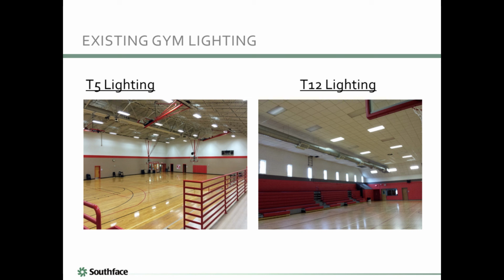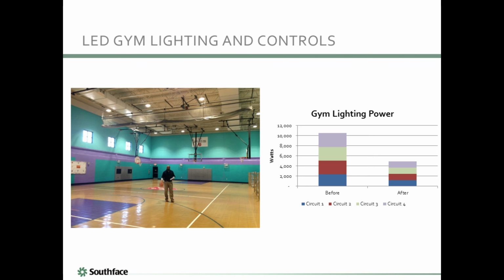So 4 out of the 6 recreation centers had already upgraded high-bay metal halide lighting to T5 or T8. 1 recreation center had converted high-bay lighting to LED. The remaining 1 recreation center had T12 high-bay lighting. High-bay fluorescent lighting requires no warm-up time and is far more efficient than metal halide.